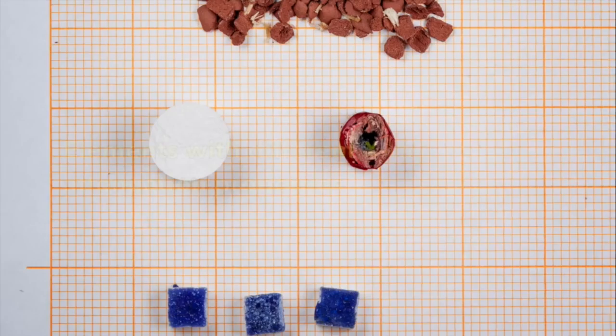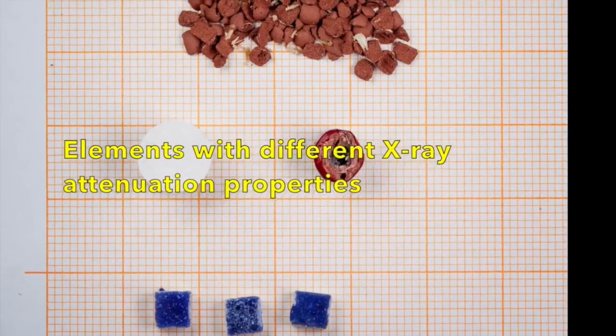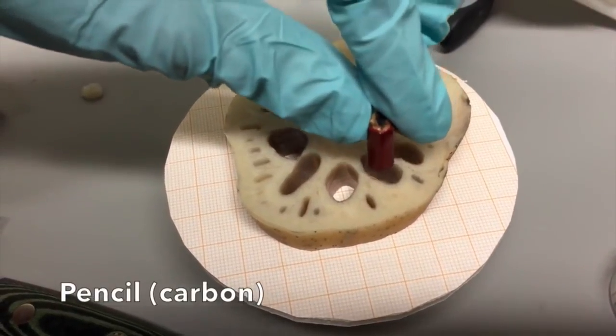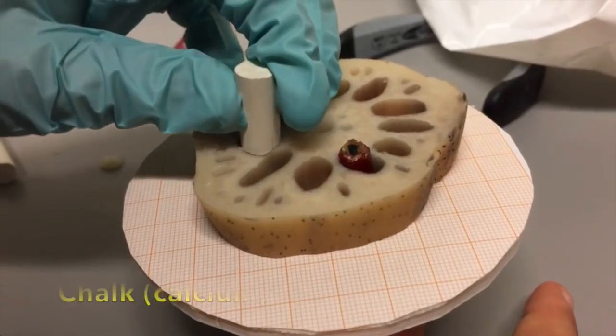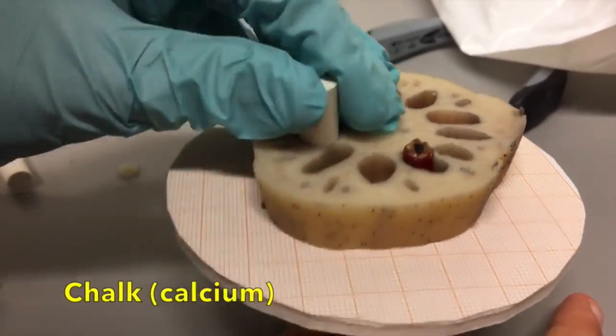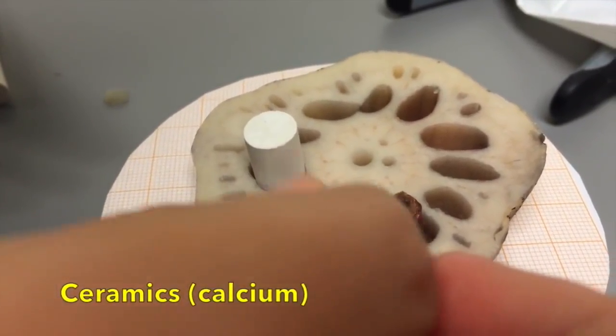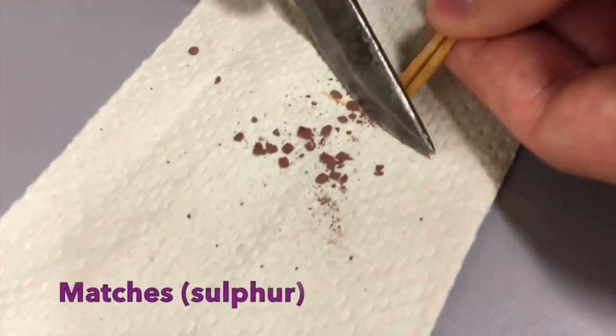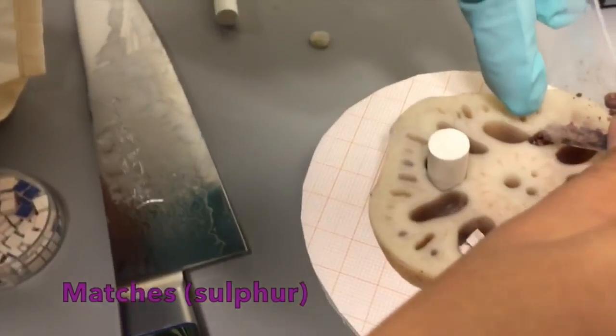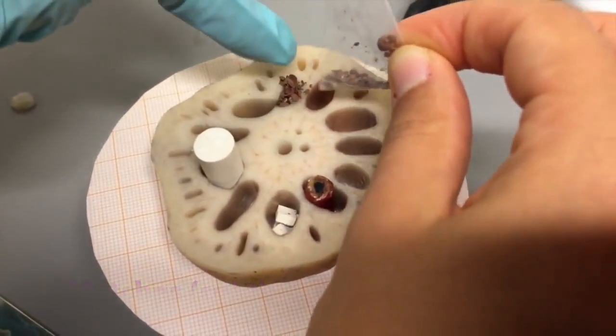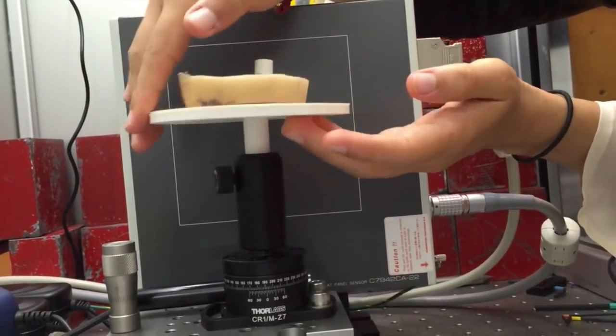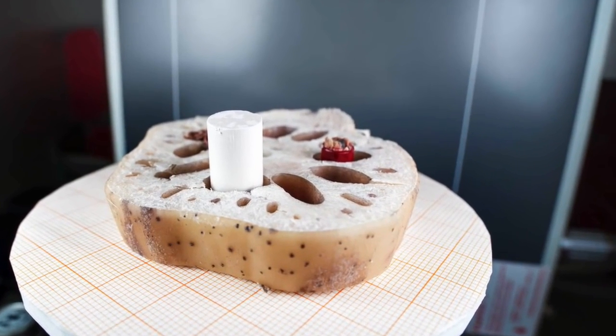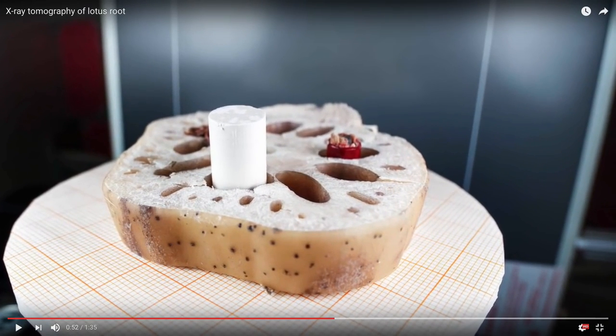So you need to pick up some kind of phantom, we will have some options for you later. There needs to be some contrast in the x-ray attenuation, in whatever you choose. Then you need to enter it inside the machine.